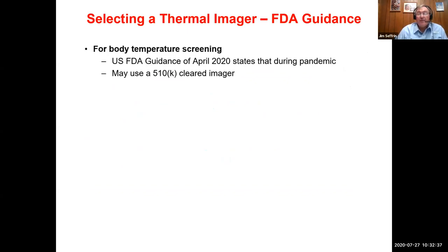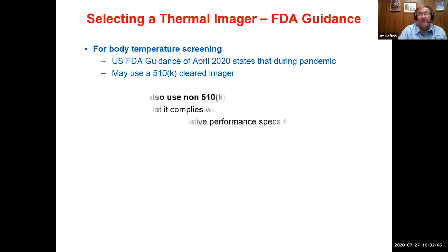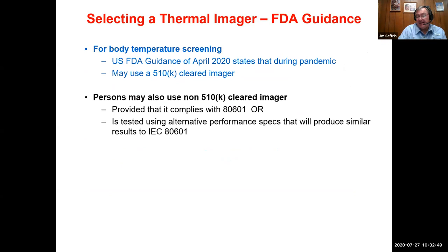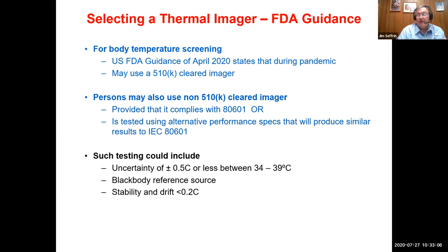So, how do we select the thermal imager? Well, if we look to FDA guidance for body temperature screening, the US FDA guidance of April 2020 states that during the pandemic, you may use a 510K cleared imager. You may also use, as an alternative, a non-510K cleared imager, provided that it complies with IEC 80601 or it's tested using alternative performance specifications that would produce similar results to that document. Such testing could include an uncertainty of within 0.5 Celsius or less between 34 and 39 C. That would be roughly 0.9 Fahrenheit. A black body reference source, and the stability and drift must be less than 0.2 Celsius or 0.36 Fahrenheit.